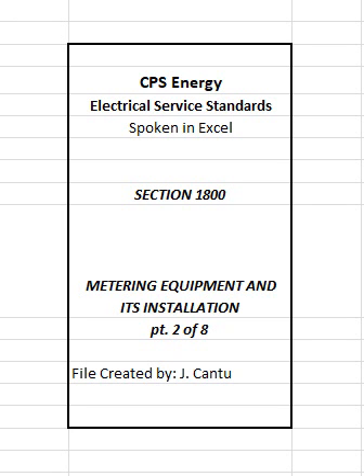Where service is overhead, the line conductors will enter the top of the transsocket and connect to the top terminals. Load conductors will always exit opposite the line conductors, and conductors will not be allowed to cross inside the transsocket. The conductor entrance/exit location notes must be followed. Refer to Table 1801 and Figures 1818 and 1819 for more specific and detailed information related to transsockets.